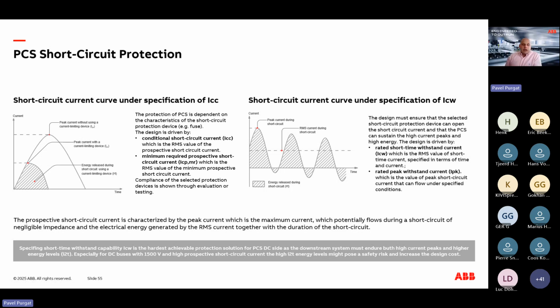fuse, of course, is that as you increase the current rating of the fuse, the let-through energy of the fuse is also increasing. And what can happen when you need a fuse for 1, 2, or 3 kiloampere is that the let-through current of the fuse will be anyway the first peak, and the fuse, based on the energy, will react somewhere here. So the utilization of fuses also has some limitations in these DC systems.